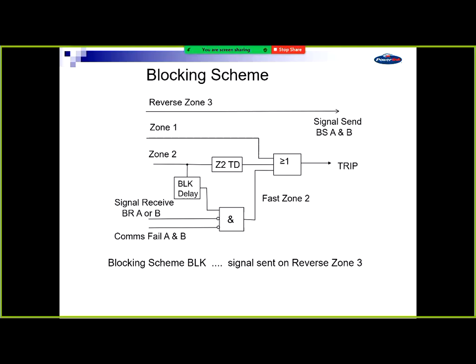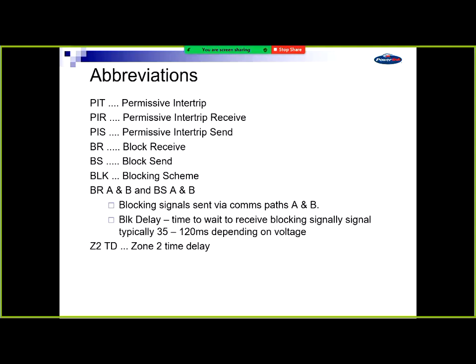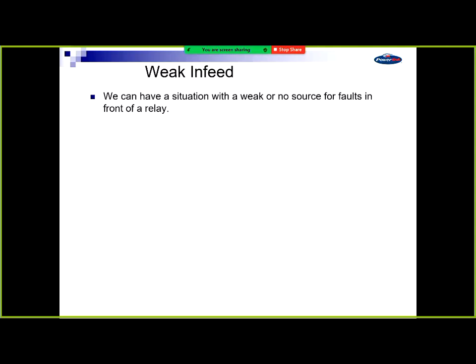All of this protection signaling, as I said, is getting things going quicker. So we've got that block time delay on zone 2 that you wait. So you see it in zone 2, we wait, you go through that AND gate. If we don't receive a block A or block B, and we don't have comms failure on both of them, we go through after that short blocking delay, which allows the signal to be received, and then you trip quickly. They're just a whole lot of abbreviations.